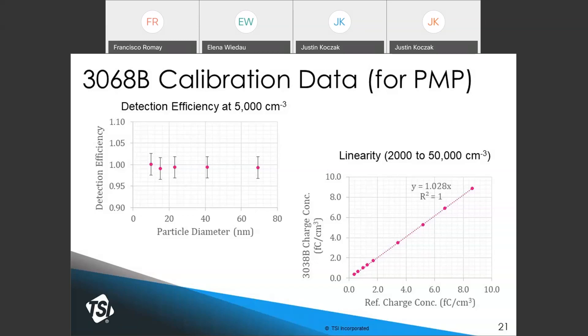A Faraday cage electrometer has nearly 100% efficiency all the way down to 5 nanometers — a nice advantage over CPCs. Detection efficiency is nearly 1 for different particle sizes tested at 5,000 particles per cc. Linearity of the TSI electrometer against a reference electrometer from a national laboratory shows nearly perfect linear correlation, with a slope of 1.028 for this particular case.